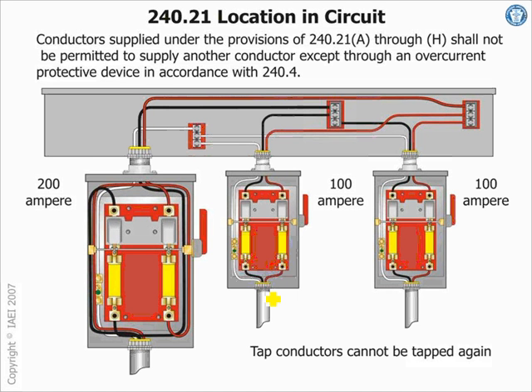So here is you tap your feeder. You tap it with whatever hardware you use with them. So looking at this one, guys, if that was a 100 amp, what minimum overcurrent protection device do I need here? Maximum 10 feet. If this is 100 multiplied by 10, the maximum that you can put right here is what? 1,000. Because 1/10 of 1,000 will give you 100. Here's the fuse 100, the conductors are 100. So you covered these. Now if you put 200 here, you just basically have a bigger conductor.